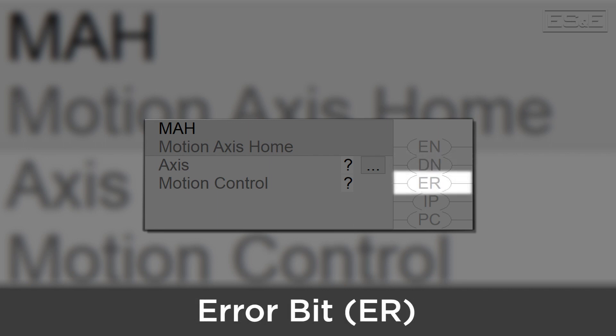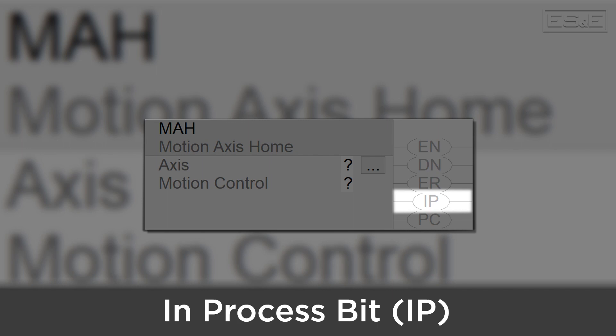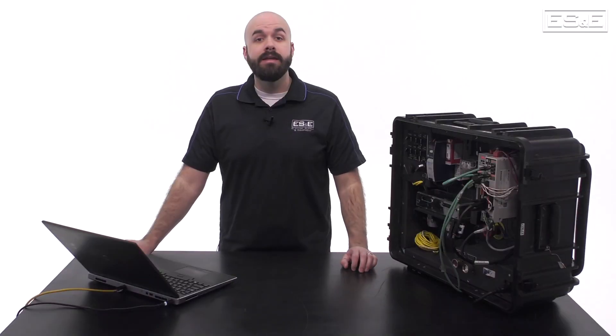The ER, or error bit, will be true when the Motion instruction executes with errors. The state of the ER bit will also only update when the enable bit transitions from false to true. The IP, or in process bit, will be true while the instruction is currently running a task and has not yet finished. The PC, or process complete bit, will be true when the instruction finishes running its task.